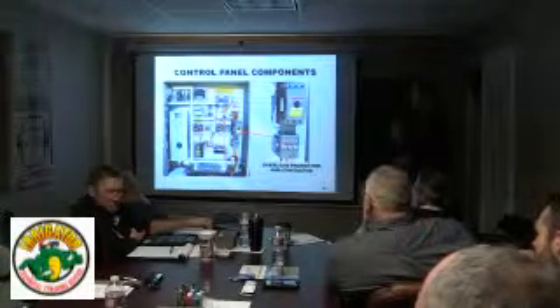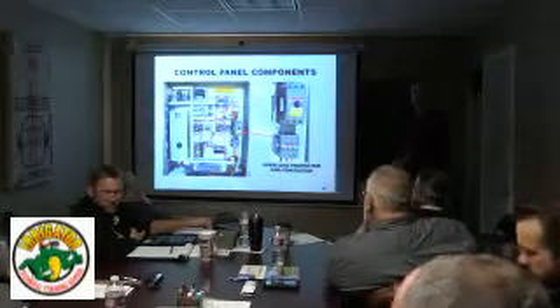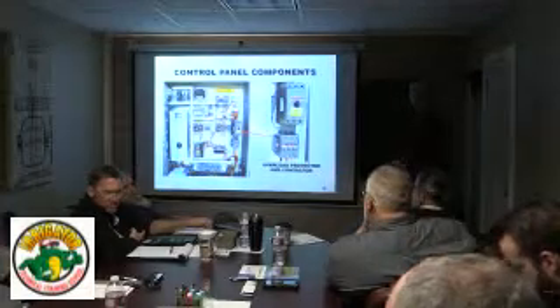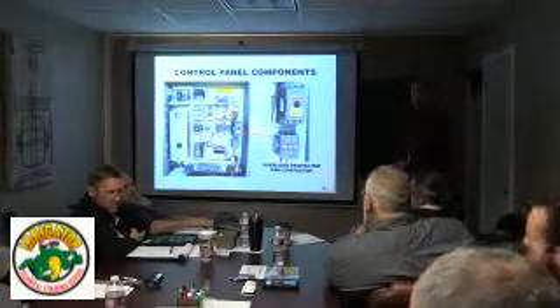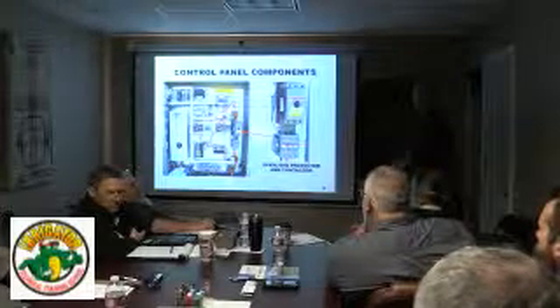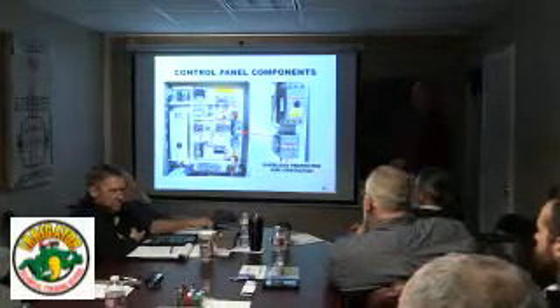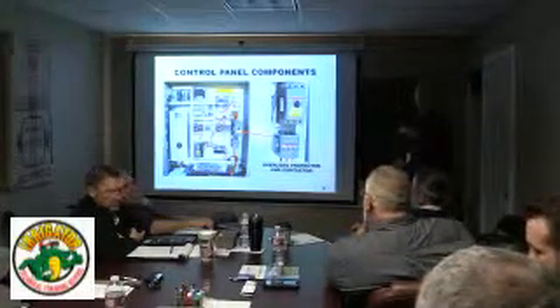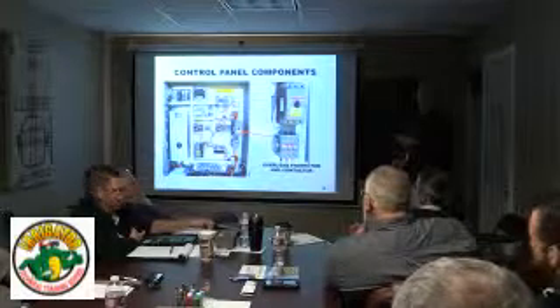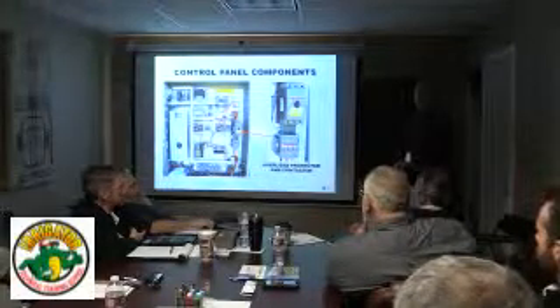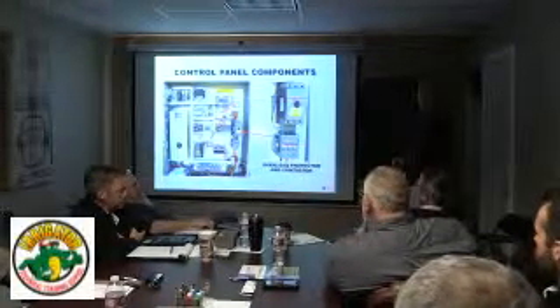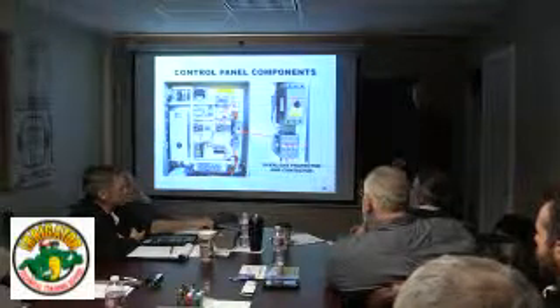So you're basically sending a VFD enable signal from the PLC to the VFD when you want to start the motor. Yes. And then a speed reference. Our hand-off-auto switch will go to the PLC first, and then we'll output from the PLC to the drive.